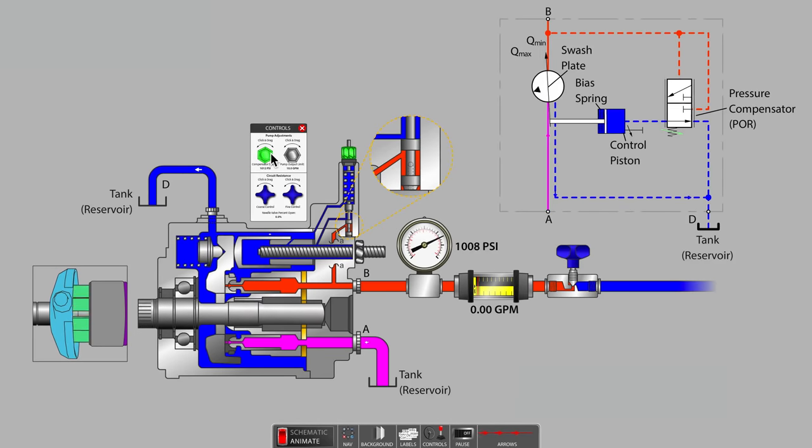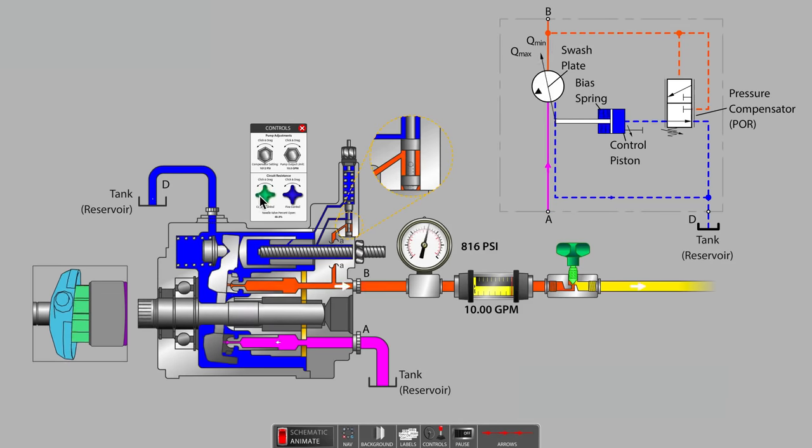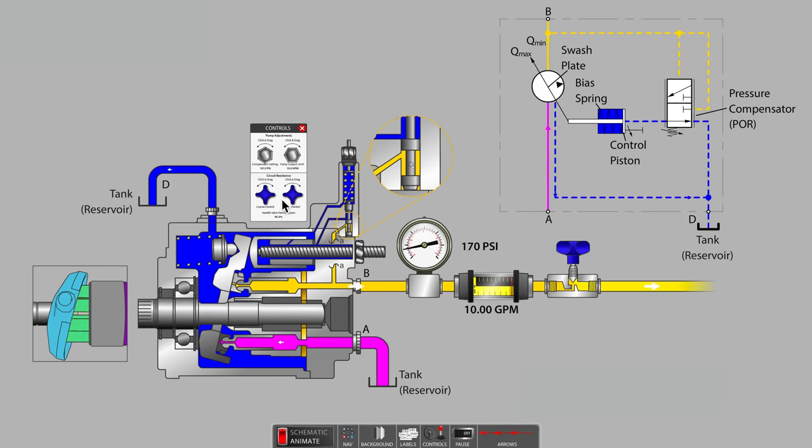When we open the needle valve, pressure will fall and the pump will return to maximum displacement due to the force of the bias spring. That is the meaning of the bias spring. The bias spring means that the pump has a tendency to produce maximum flow whenever possible.